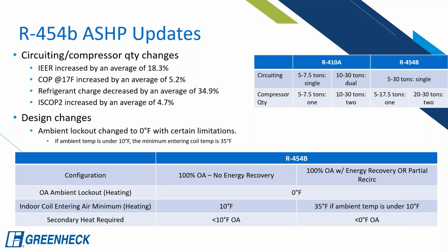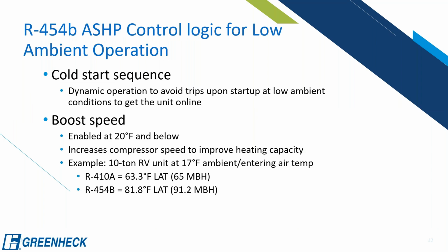So if the outdoor air temperature goes below 10 degrees, then you'll need to have some sort of backup heat involved, and we can also do an electric preheat coil as well. So some control logic changes with this low ambient operation. Our cold start sequence is designed to start up in low ambient. We have a dynamic control operation that basically avoids trips upon startup at low operation condition.